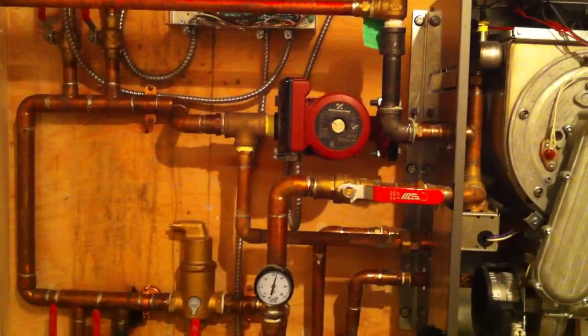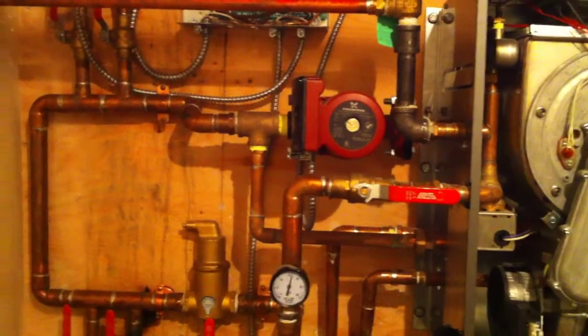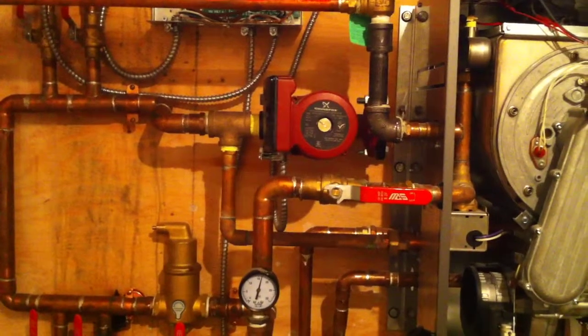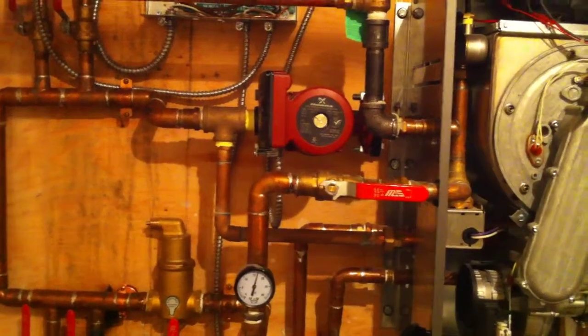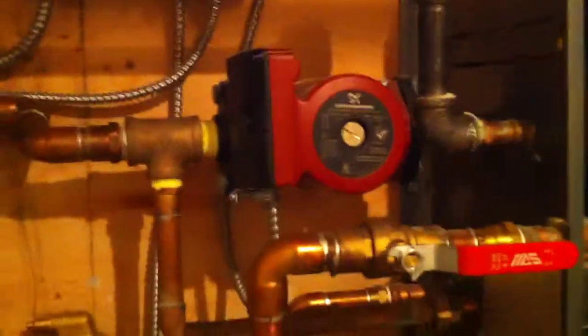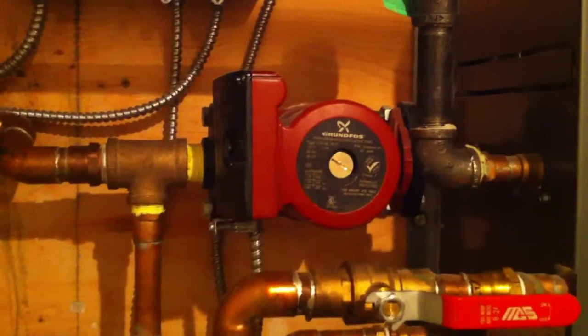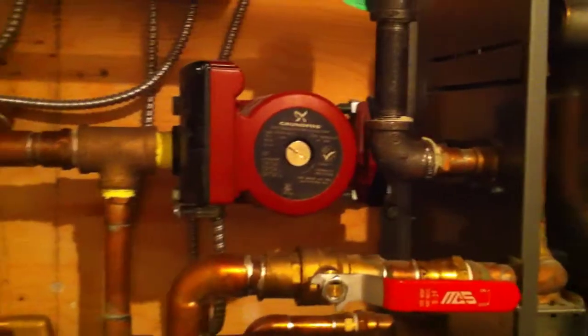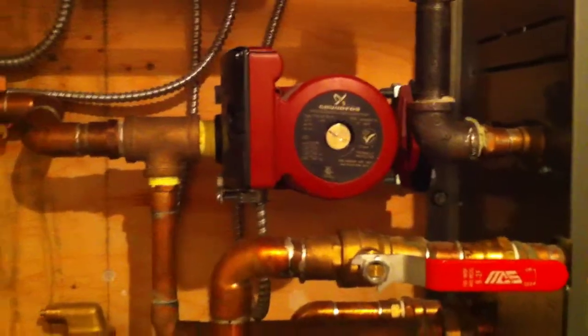This is kind of a goofy setup. You've got one pump that runs the basically high temperature and low temperature. So this one pump here runs whenever the boiler runs. That's your primary loop. If there's a call for infloor, it'll run that, and it goes through this loop here.